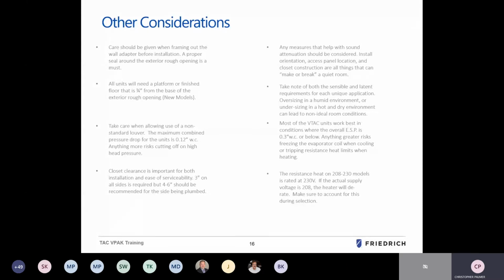Most of the VTACs work best in conditions where the overall external static pressure, or ESP, is 0.3 inches or below. Anything greater, and you could risk freezing the evaporator coil, creating overheating issues, air restrictions, and heat limits when heating. And also, be mindful of this.